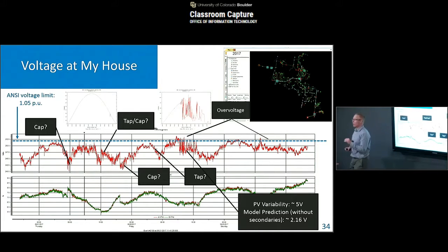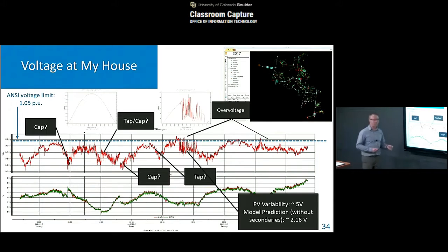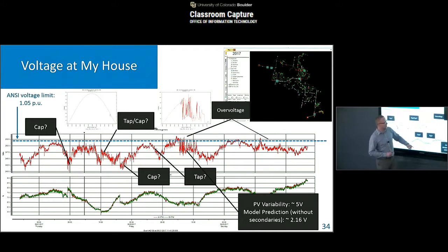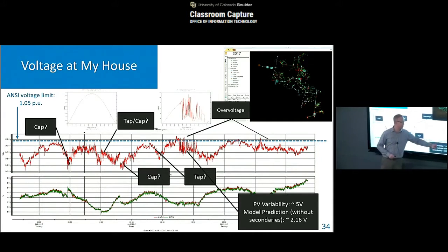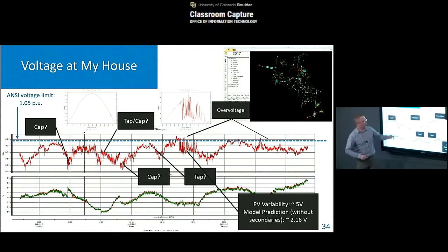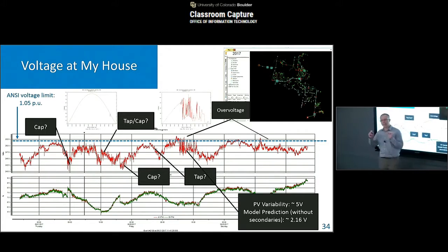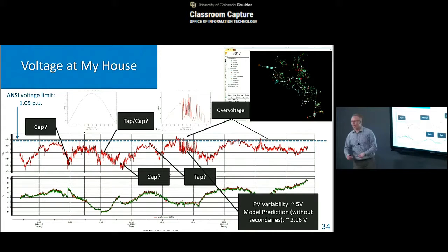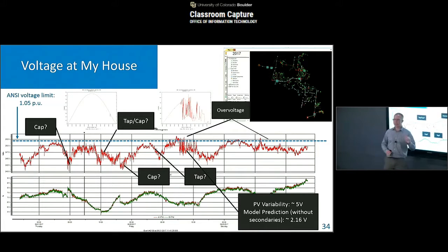Now, I was talking before about modeling secondaries and how important that is. The reason why that's so important is the measured data shows a PV variability at my house of about 5 volts during some of these events. Right? Remember, your limit is, so that's about half of your limit between nominal and the upper limit. If you don't model the secondaries, if you don't model that last 30 meters of wire to your house, that's where you get the biggest losses, right? Or the rise if you have PV.